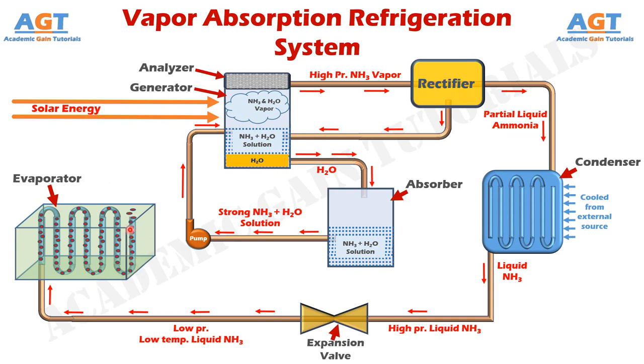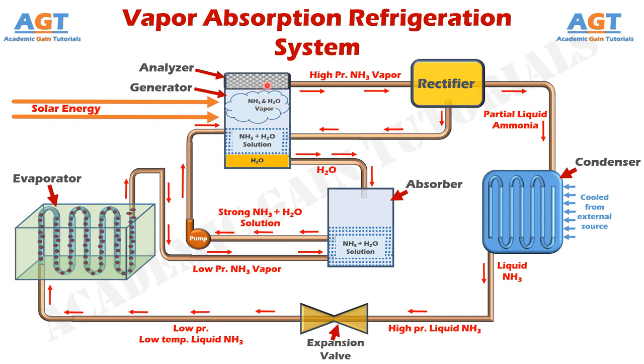After that, this low pressure ammonia vapor will leave the evaporator and enter the absorber again through this connecting pipe. Then again, this low pressure ammonia vapor will form a solution with the water present in the absorber. The pump will again send this solution to the generator, where the heat generated by solar energy will again form ammonia vapor and water vapor. Then again water vapor is sent back to the absorber, ammonia vapor passes through the analyzer to the rectifier, and the whole cycle keeps happening over and over again. And thus refrigeration occurs continuously in the evaporator, and the surrounding space keeps cooling continuously. So, this is how a solar vapor absorption refrigeration system works, where solar energy is used to obtain the cooling effect. Thank you for watching this video.